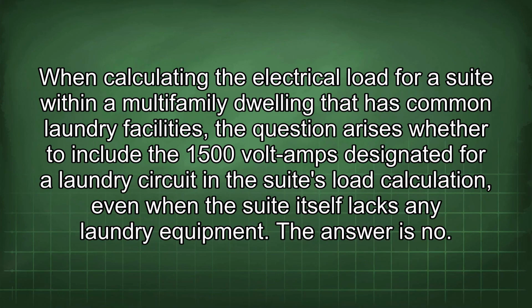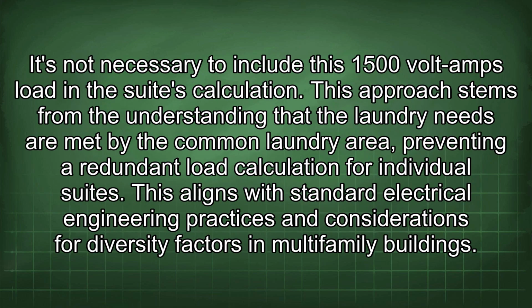When calculating the electrical load for a suite within a multifamily dwelling that has common laundry facilities, the question arises whether to include the 1500-volt amps designated for a laundry circuit in the suite's load calculation, even when the suite itself lacks any laundry equipment. The answer is no. It's not necessary to include this 1500-volt amps load in the suite's calculation.